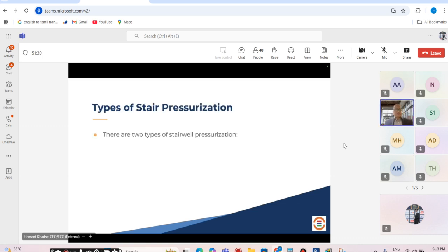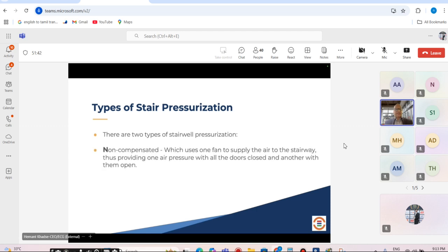So when you also design the pressurization, there are essentially non-compensated or compensated ways to do that. That means when you expect some of the door openings or the evacuation process that is expected in that particular building, which will allow the fresh air to get diluted, the pressurization, you have to include that in your calculations and then design your CFM capacity of your fans.